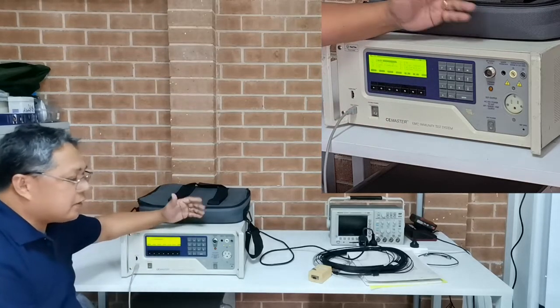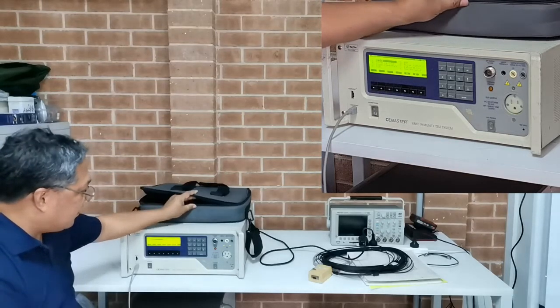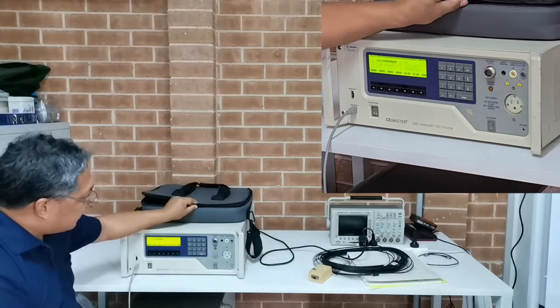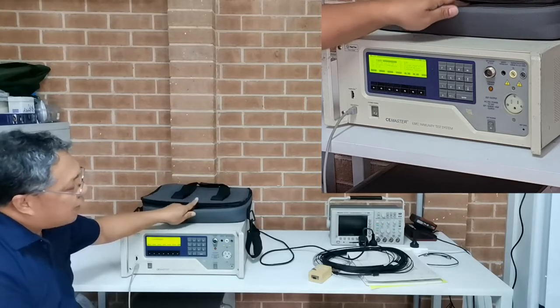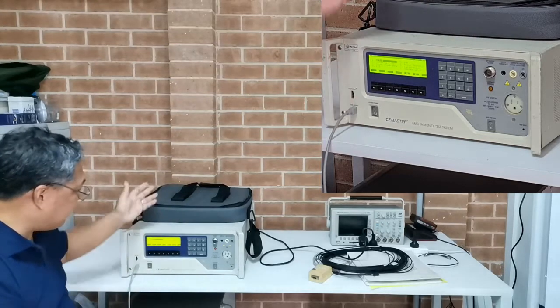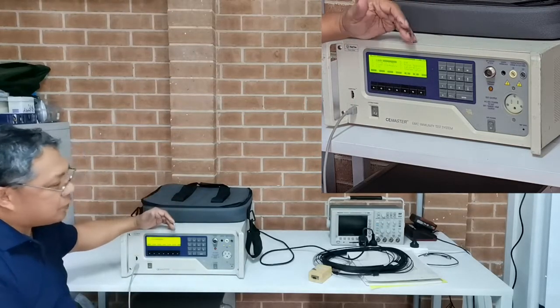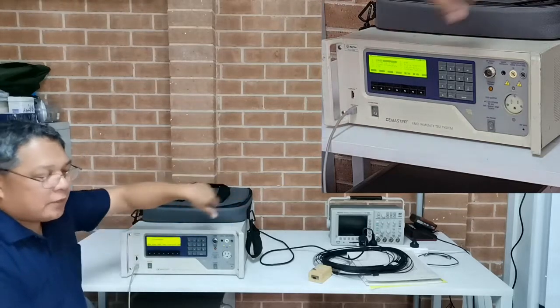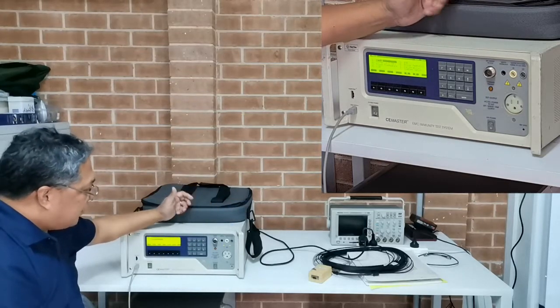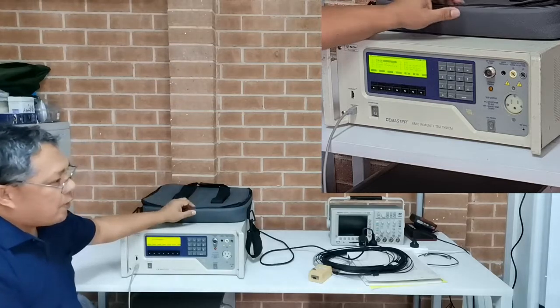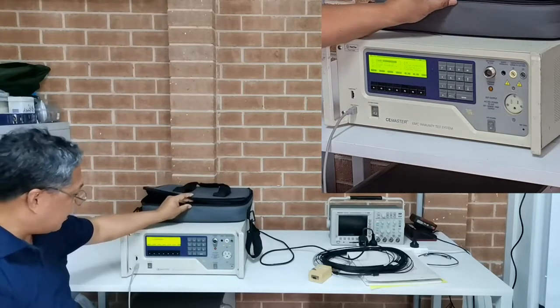So the number 6 is the pulse magnetic. Pulse magnetic is the 61000-4-9. That's the one where you're applying a surge pulse of 1.2/50 microsecond into a magnetic loop, into a single loop of magnetic. Some standards require that 61000-4-9 as well.